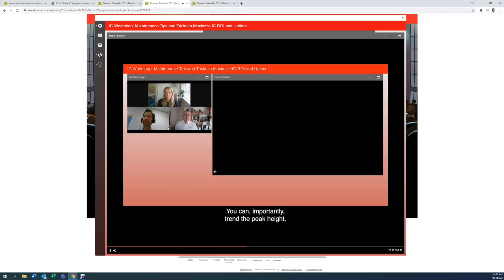So you can trend the retention times. You can, importantly, trend the peak height, and that again is a really powerful troubleshooting tool that you'll find within Chromeleon. People don't realise, they think it's there for other reasons, but as an engineer, it was the most useful part of the system, because once you overlaid all those plots, you'll find the outlier. And when you find the outlier, you know the day that the instrument went wrong. And then you go through the audit trail on that day and you'll find something happened that day. And again, it's a very simple tool to use. You don't need to have a service engineer on site to do that. You've got all that information in the computer within Chromeleon, within your ion chromatograph, to tell you that already.